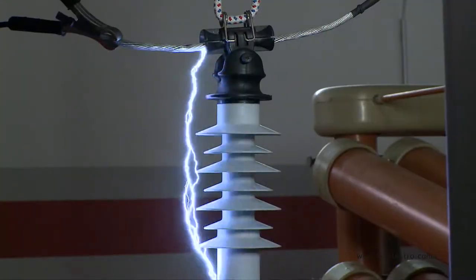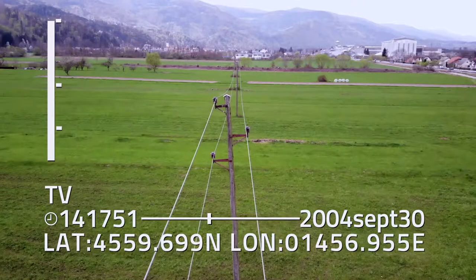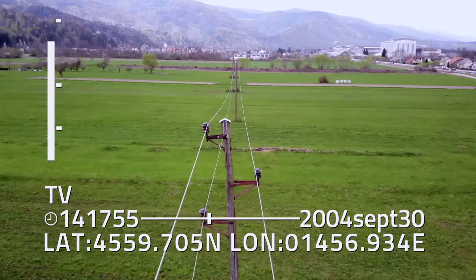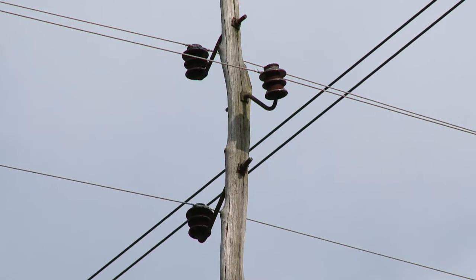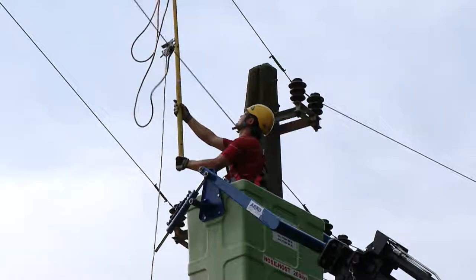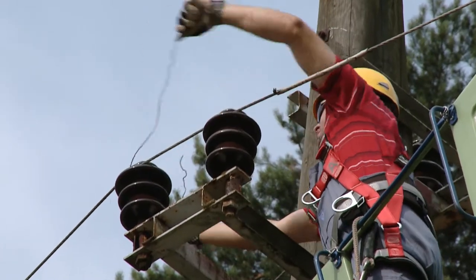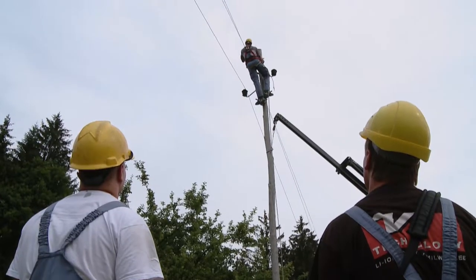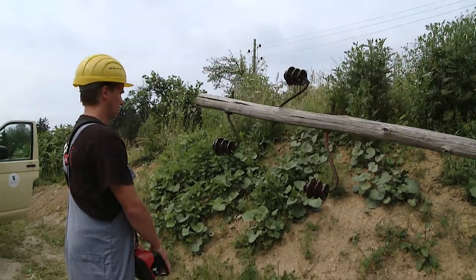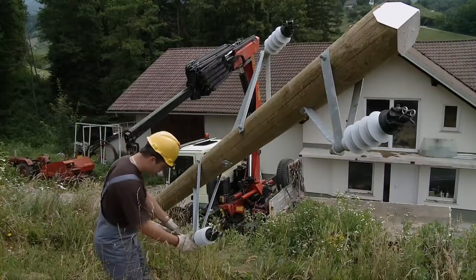Various studies, lab research, and measurements performed on overhead power lines have demonstrated that excessive electric field strength and resulting partial discharges are likely to occur at a bare conductor's fixation point onto an insulator with a metal end fitting. This may lead to the conductor burning off from its place of fixation after long term use because of partial discharges.